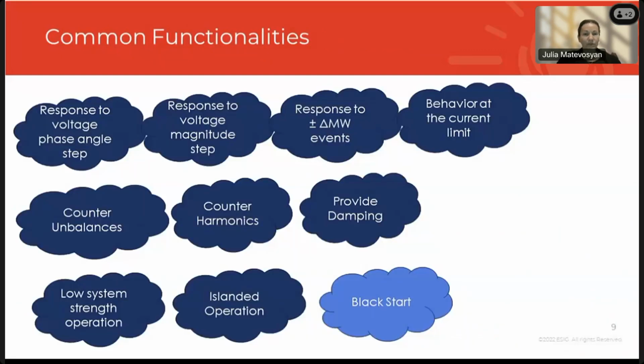All right, so let's move on to the next one. If I look at the common functionalities that are required, there will be some on this slide that are not in every requirement, but overall you'll see these common themes throughout all of the requirements. And I think it's a good sign that we're all at a high level on the same page of what is needed. So these are response to voltage phase angle jump, response to voltage magnitude step, response to sudden change in megawatts, so either load trip or generator trip, behavior at current limit. This one is not specifically defined in some of the requirements. Some of them will say what's expected, and some of them don't have it. Counter imbalances and counter harmonics. Provide damping, low system strength operation, islanded operation, and then black start.